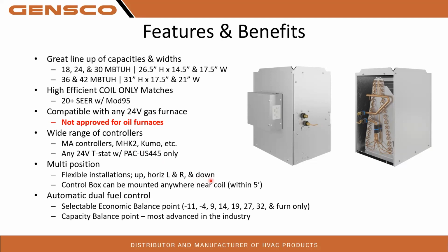These coils are multi-positional. They come set up for either horizontal left, right, or vertical up or down, so that gives you some options to play with. The control box, which is this right here, where the brains of the operation are, can be mounted anywhere. It does not have to be on the coil. It can be mounted on the wall, the ceiling, or the floor, as long as it's within 5 feet of the coil. The reason is that the coil thermistors have to plug into that coil box. They cannot be spliced, and you've only got about an 8-foot cord. So you need some extra slack to be able to get in there without too much tension on them. So, within 5 feet.